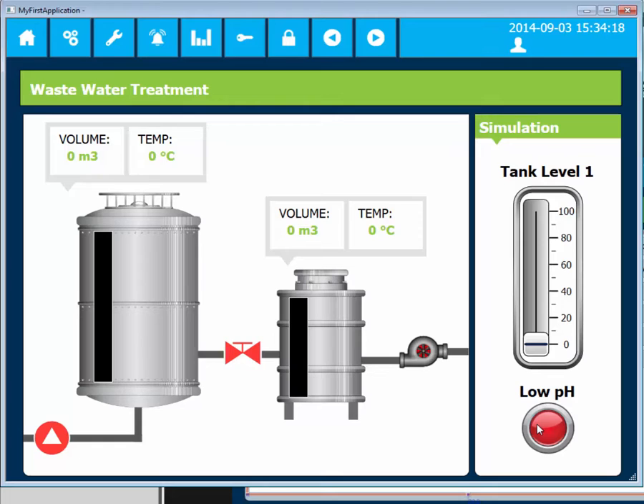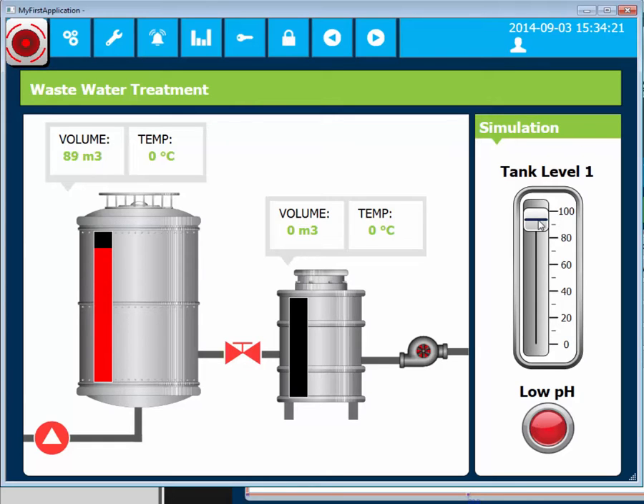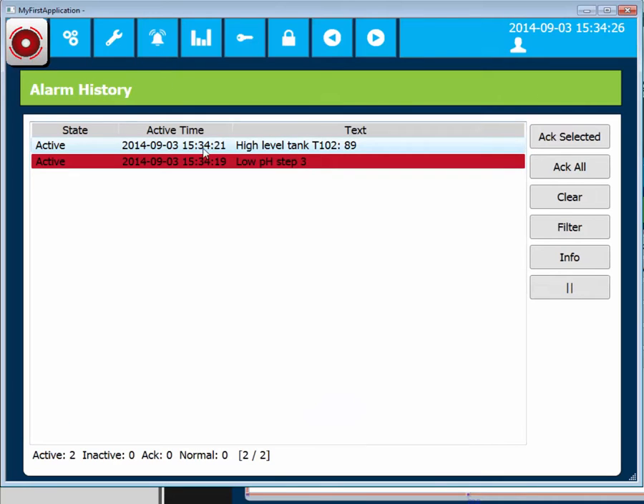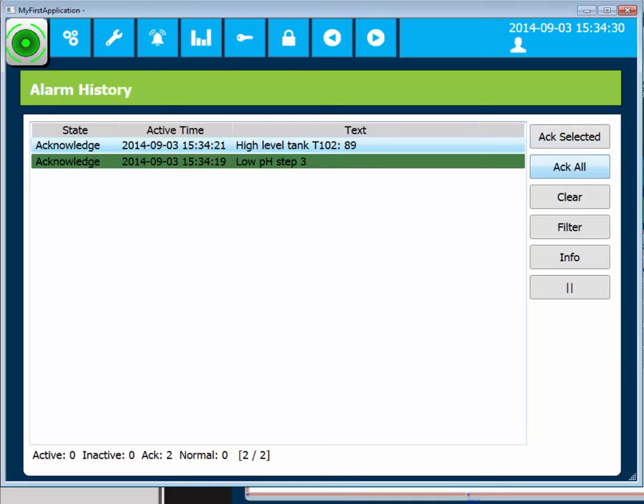The second alarm is generated when the tag at Tank Level 1 is greater than 85. By jumping to a screen with Alarm Viewer object, the operator can see the alarm history as well as acknowledge the alarms.